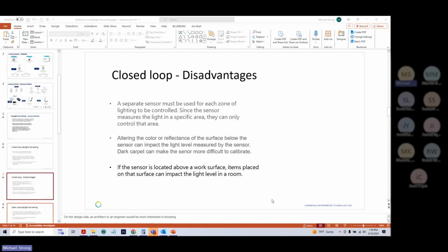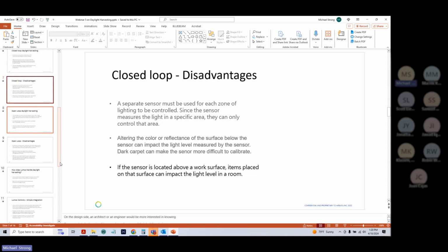Altering the color and reflectance of the surface below the sensor can impact the light level measured by the sensor. Now, for most of us, that's an engineering and architectural design. That's nothing to do with us as electricians or electrical distributors or even as a manufacturer. But knowing that the lack of reflectance coming from a floor, let's say, that is charcoal or black or gray, compared to, say, a white marble floor, knowing the difference between the two helps us in designing not only our lighting, because a lot of what lighting is based on is reflectance. So if the sensor is located above a work surface, items placed on that surface impact the light level in a room. I think that goes without saying. All of this here is kind of a no-brainer, but these are some of the disadvantages to a closed loop system. But it is by far the most popular form and one that we can easily implement.